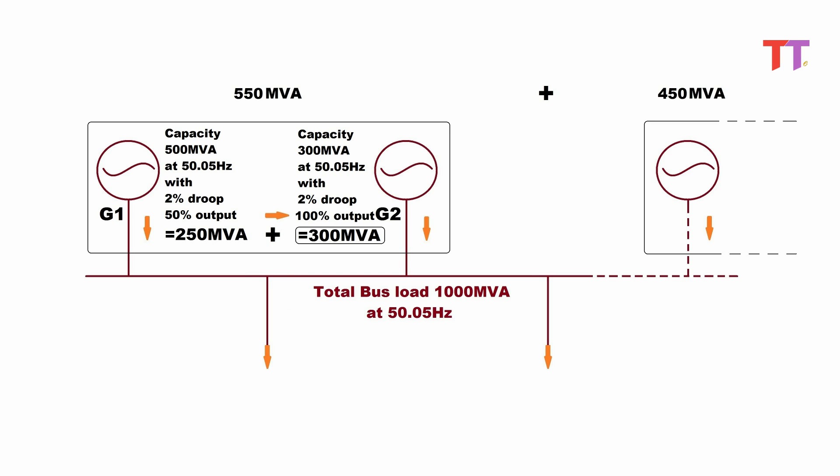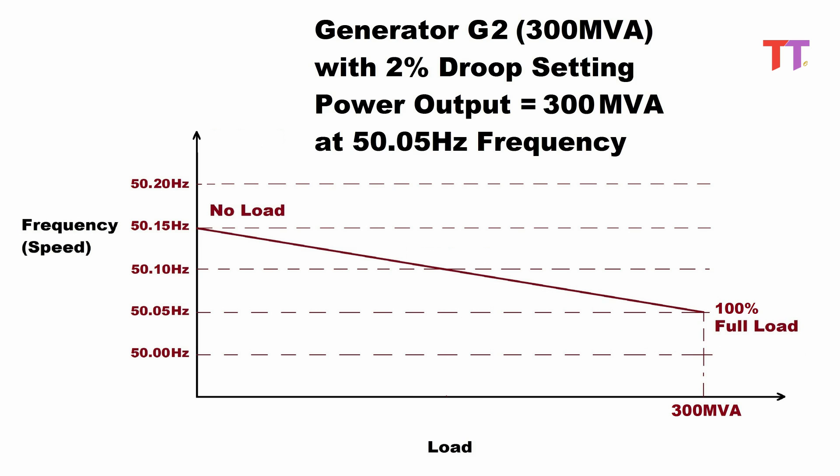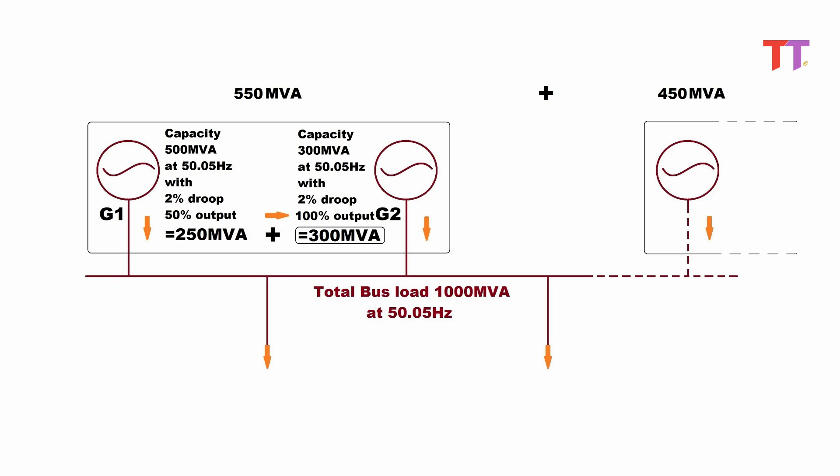Now let's say we want to load generator G2 at 100% of its capacity, delivering 300 MVA load. So the speed reference for G2 is raised to 50.15 Hz from 50.10 Hz. With the new droop setting, G2 is loaded at 100%, delivering 300 MVA load at 50.05 Hz frequency, which is bus frequency. Now generator G1 and G2 deliver 250 MVA and 300 MVA load respectively. That means out of 1000 MVA load demand of the bus, 550 MVA is supplied by G1 and G2, and the rest 450 MVA is supplied by other generators running in parallel.